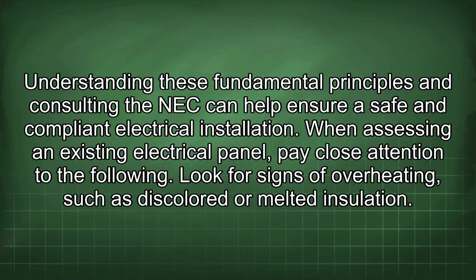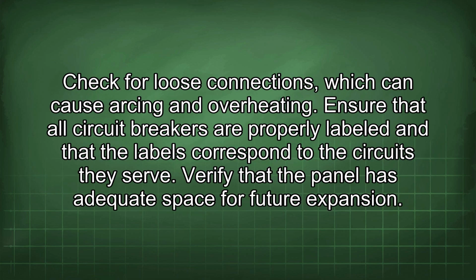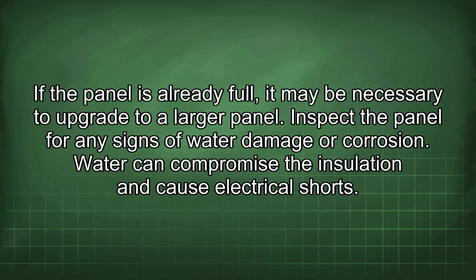When assessing an existing electrical panel, pay close attention to the following. Look for signs of overheating, such as discolored or melted insulation. Check for loose connections, which can cause arcing and overheating. Ensure that all circuit breakers are properly labeled and that the labels correspond to the circuits they serve. Verify that the panel has adequate space for future expansion. If the panel is already full, it may be necessary to upgrade to a larger panel.